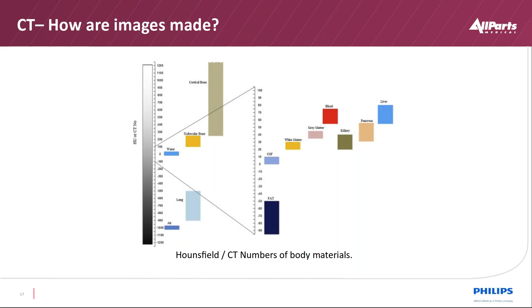We have to guarantee this scaling system works for a CT scan to be considered valid. So a lot of QA is involved with image quality analysis to validate our CT numbers are within spec, okay? So when we go back to look at an image now, remember we talked about how we actually acquired it with a thickness, a slice thickness. So every spot on the image would be an average of that. So if it's a 1 millimeter scan, there'll be an average of material of 1 millimeter that we're looking at as far as a thickness.